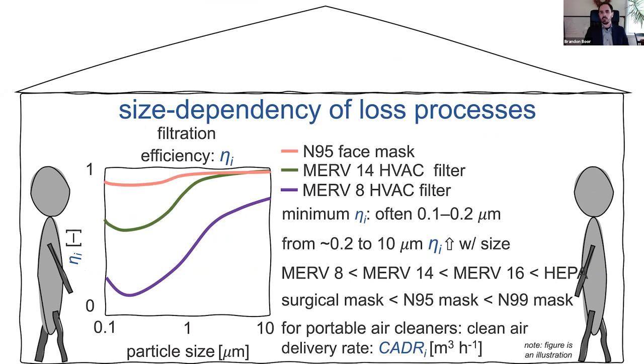This is pertinent to HVAC filter media and portable air cleaners, as well as face masks. And this is strongly size dependent. And we see that for particles above a micron, the efficiency tends to increase, but there's generally a minimum between 0.1 and 1 micron. So this filtration efficiency tends to have a U-shaped curve. So these smaller particles below a micron, which our respiratory activities produce an abundance of, are the most challenging to remove with different types of filter media.